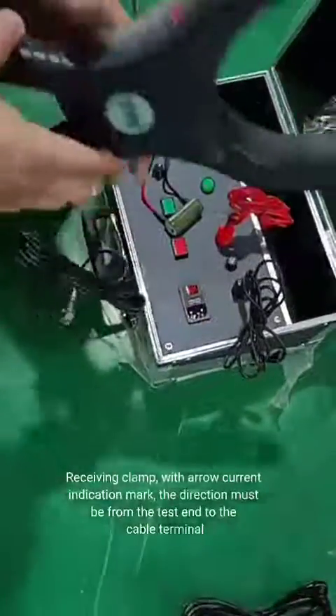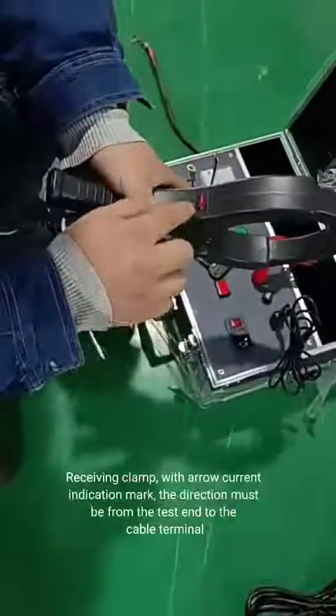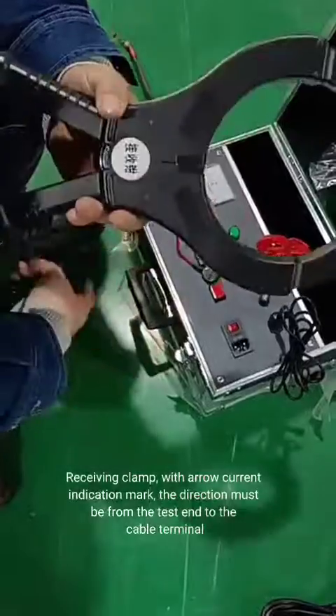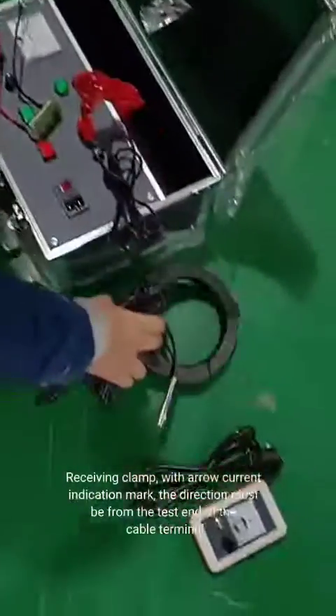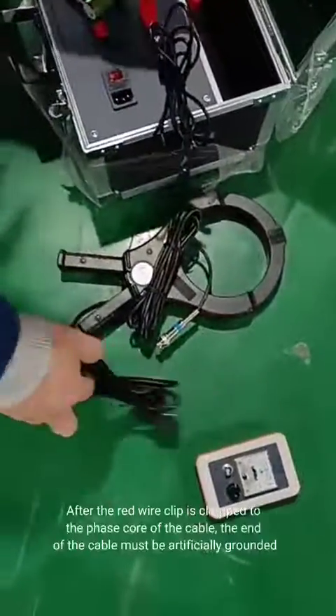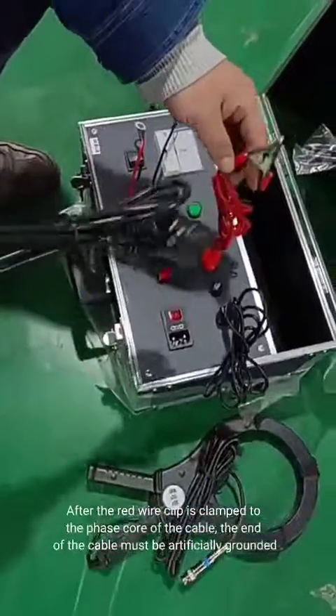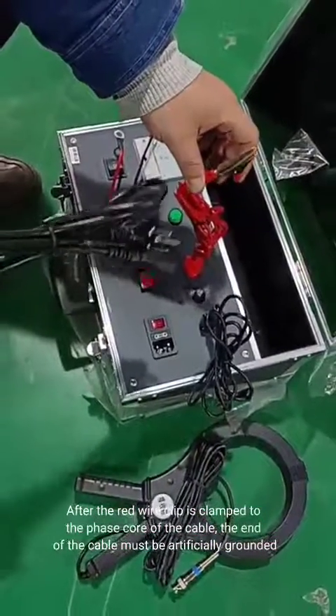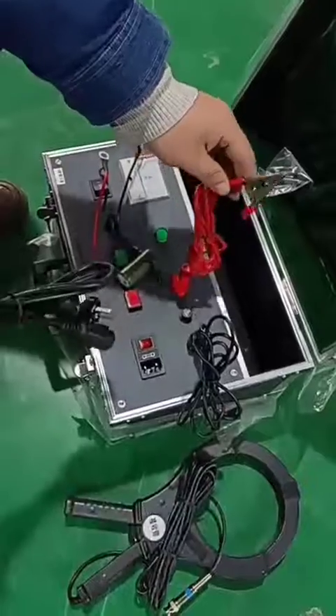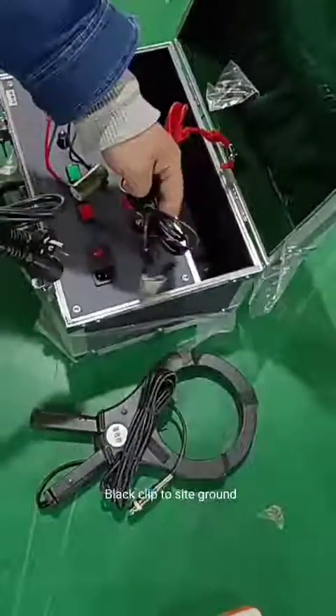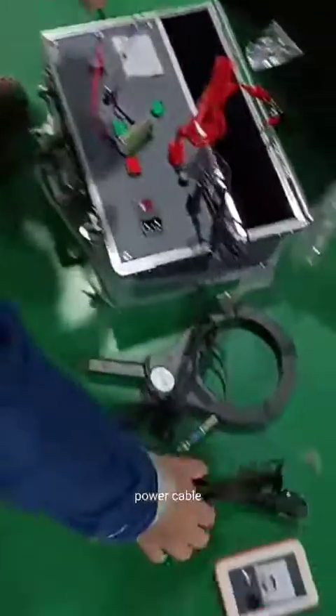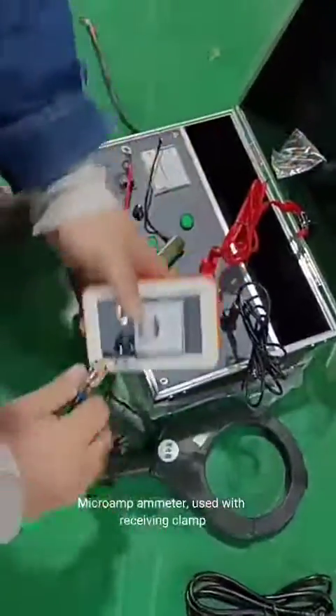Receiving clamp with arrow current indication mark. The direction must be from the test end to the cable terminal. After the red wire clip is clamped to the phase core of the cable, the end of the cable must be artificially grounded. Black clip to site ground. Power cable. Microamp ammeter used with receiving clamp.